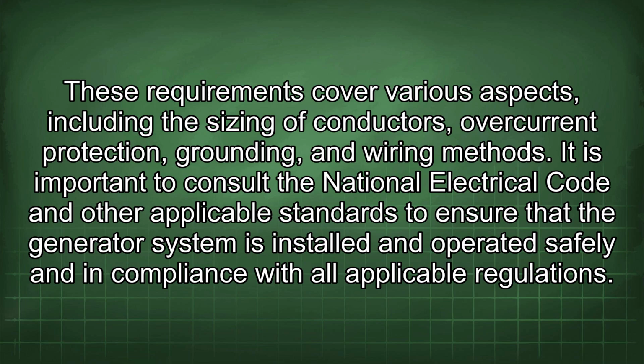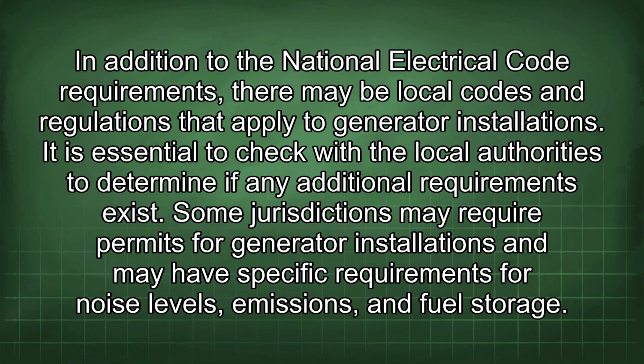It is important to consult the National Electrical Code and other applicable standards to ensure that the generator system is installed and operated safely in compliance with all applicable regulations. In addition to the National Electrical Code requirements, there may be local codes and regulations that apply to generator installations. It is essential to check with the local authorities to determine if any additional requirements exist. Some jurisdictions may require permits for generator installations and may have specific requirements for noise levels, emissions, and fuel storage.